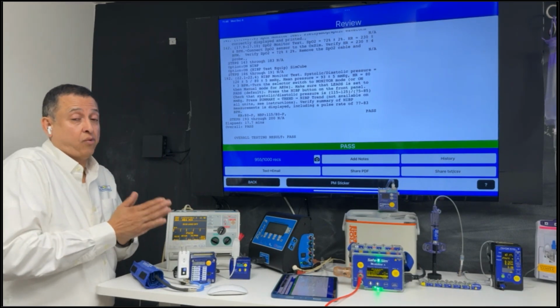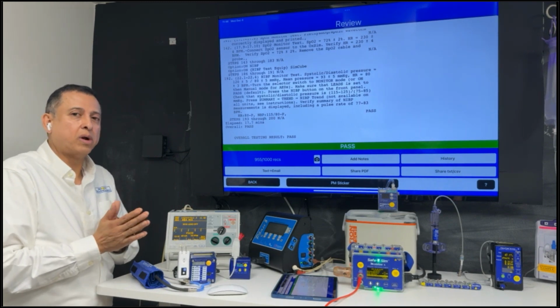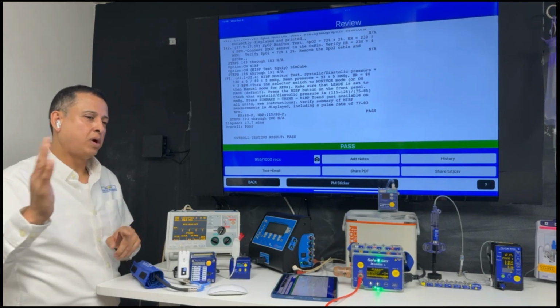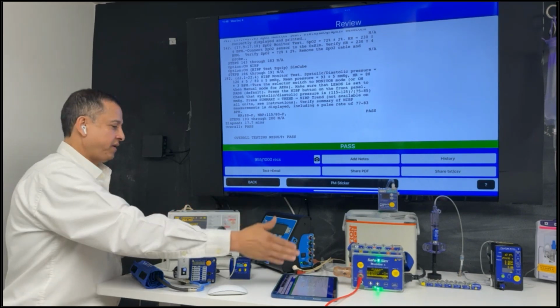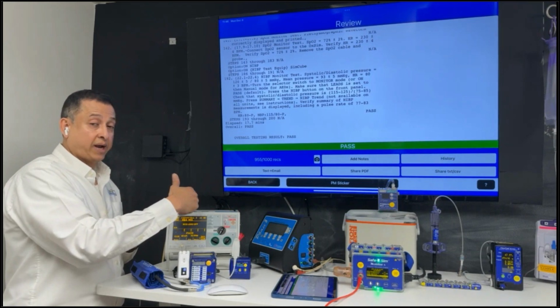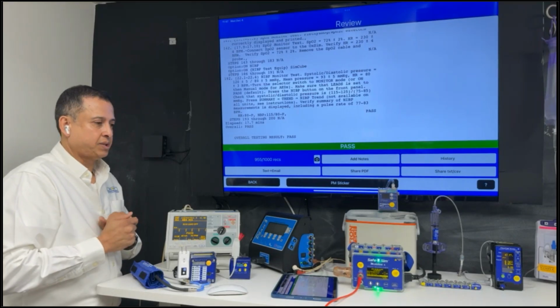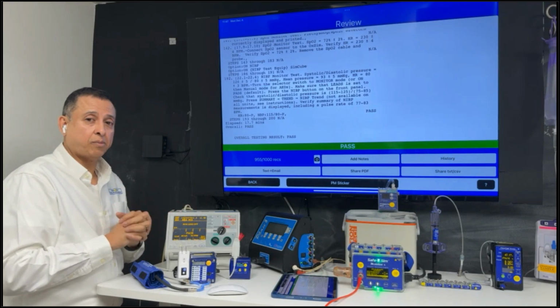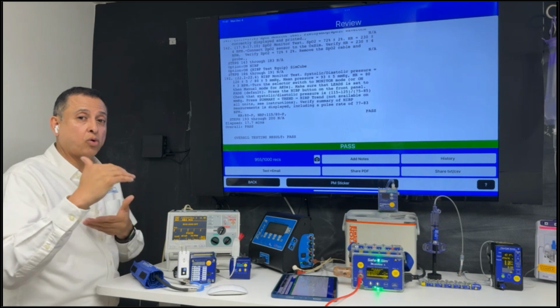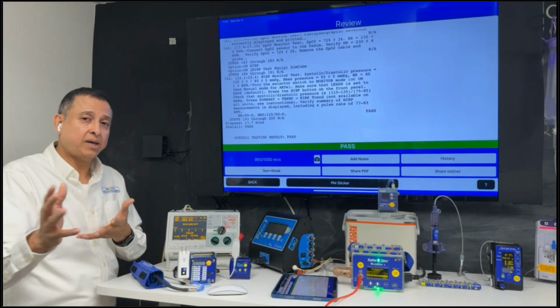Now, you also have kind of a fourth mode, which is if you want to have it controlled from your CMMS system, from your work order, we have the ability to integrate that into your CMMS so that you can just instruct from your work order, go to the analyzer, be it the safety analyzer, be it the simulators, the infusion pump analyzer, execute the tests that I require, that I programmed into my CMMS, and bring back those results live into the CMMS. So there's different integration options available up to the point where you can have full control of it right from your work orders, because some organizations want you to work from your own work order within your CMMS systems. Maybe you want to work offline, do all your work, and then come back and sync to your CMMS system.